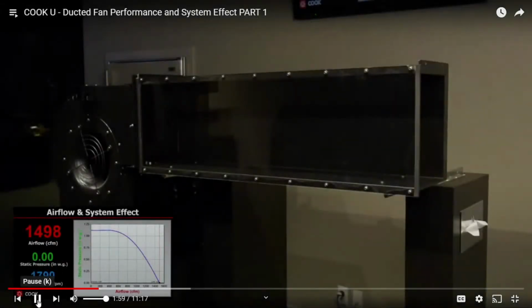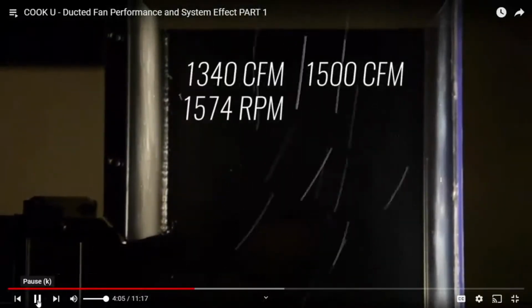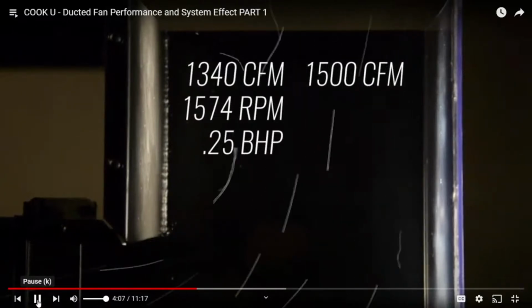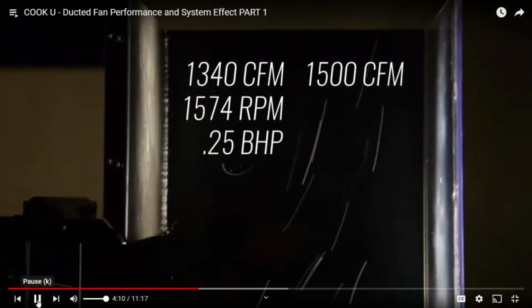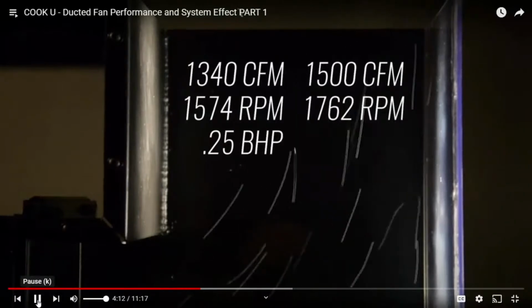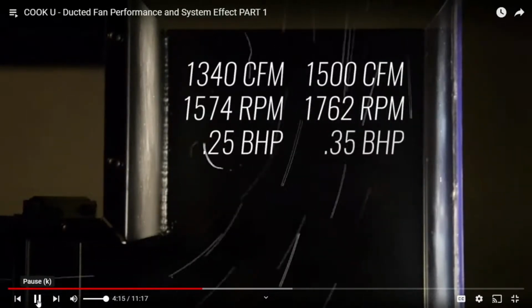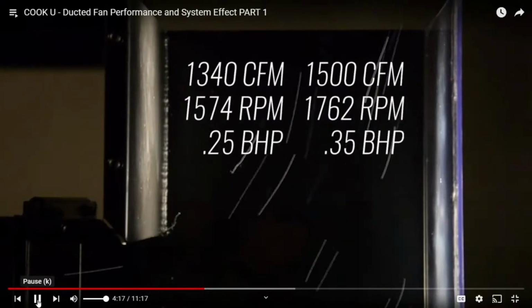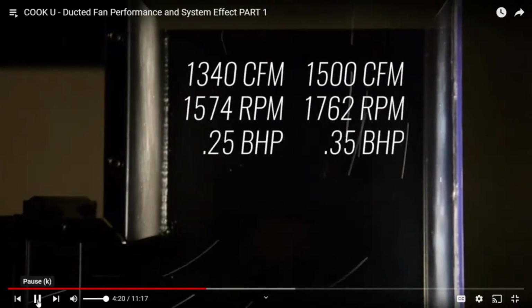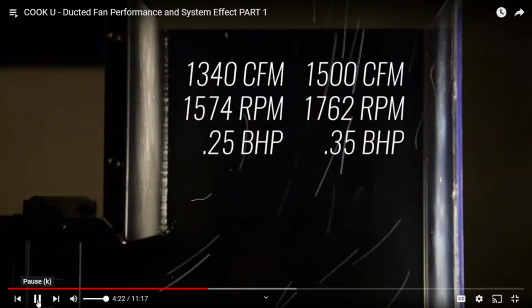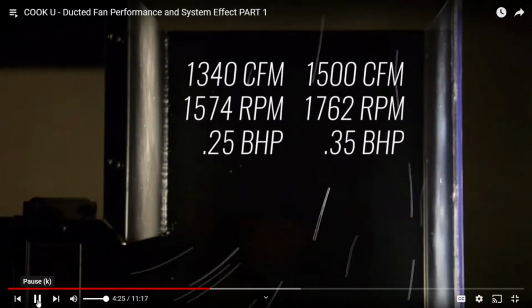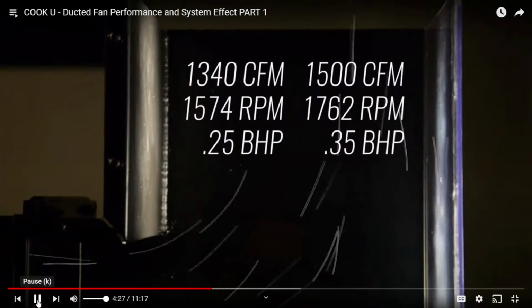Let's look at the performance of our fan with the discharge duct attached. We can see that the fan is moving approximately 1340 CFM at 1574 RPM and consuming 0.25 brake horsepower. Using the fan laws, we calculate that the fan would need to run at 1762 RPM with a new brake horsepower of 0.35 to get the required airflow. Unfortunately, in this case, the motor on our demo fan is a quarter-horse motor and would need to be replaced with a larger motor to get the required performance.